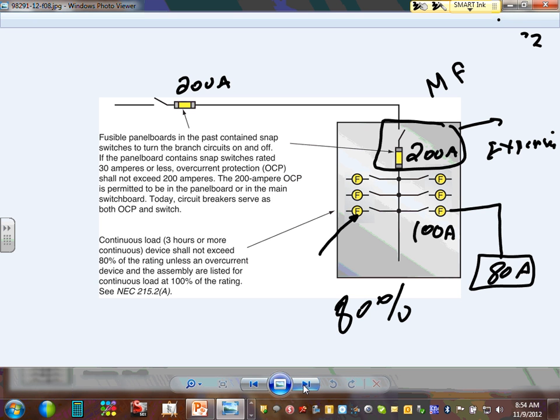Unless the circuit breaker is rated for 100%. Those only become viable if you are probably at 600 amps or higher. Even at 1,000 amps, it makes sense to put in a 100% rated circuit breaker. You guys see that 100% rated circuit breaker right here? You're talking about 1,000 amp or higher.